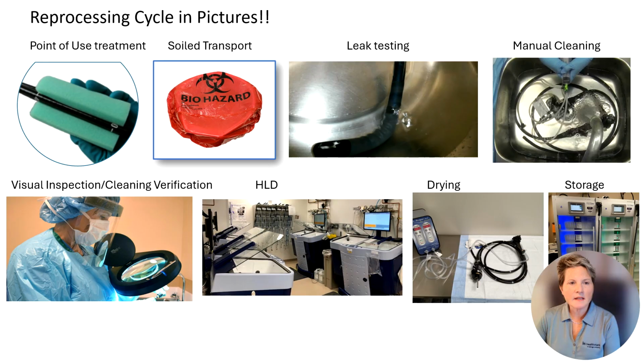And here's the reprocessing cycle in pictures. I thought this might make a little bit more of an impact and make more sense to everyone. You can see the point of use treatment is what occurs in the actual procedure room. And usually that's done by either the nurse or the technician who are assisting with the procedure. It encompasses basically sucking some fluid through the scope and using the air-water cleaning adapter, wiping down the insertion tube with a sponge similar to the one you see pictured here. And then, of course, writing down and communicating the time that the point of use treatment occurred and making sure that gets communicated to the reprocessing staff in the reprocessing room.